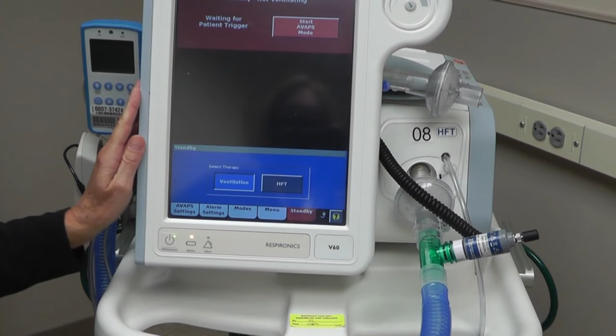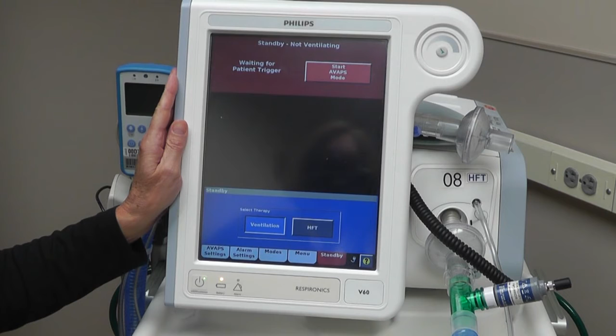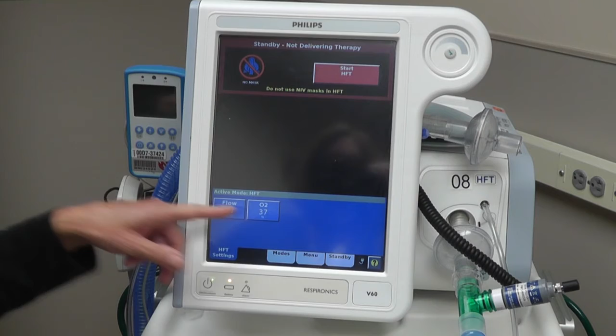The reason why we don't want you to power it off is because when we start these machines, we do have to tell it the exhalation port that is being used by the machine, and also the mask type. Those 2 things are required in order to get the proper patient leak for the machine instead of the total leak. So just entering in standby. Also in standby, you can see that we can enter into high flow therapy here with this machine, and it will have the flow and the FiO2.